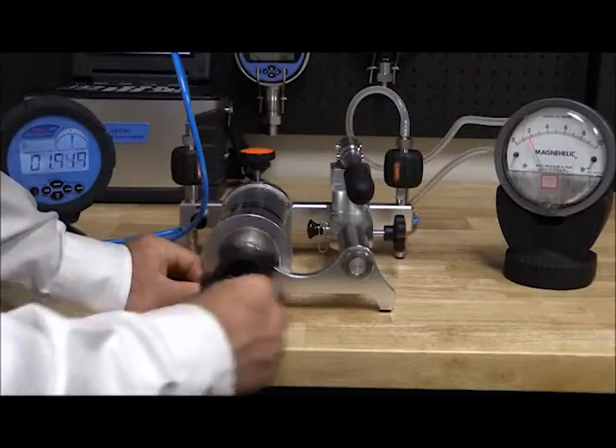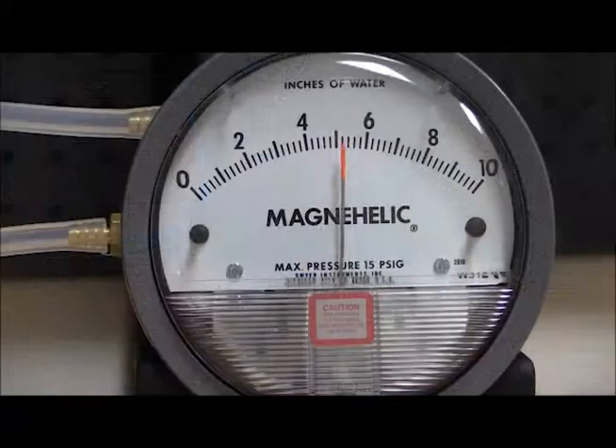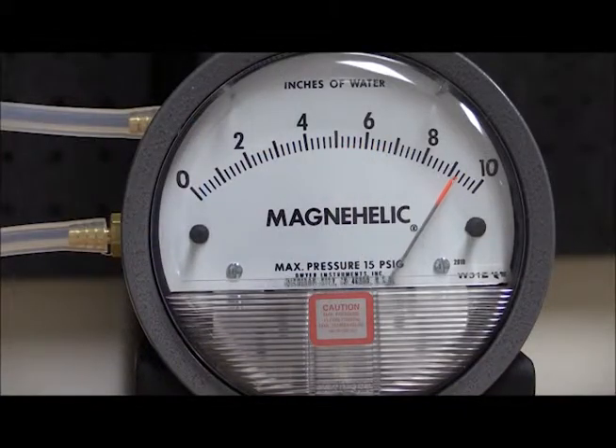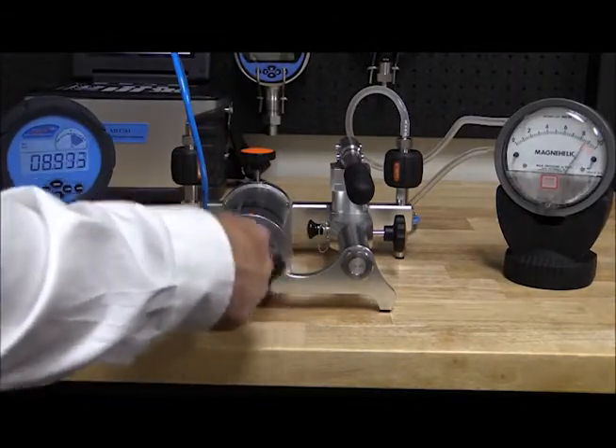Now we are ready to generate the pressure and record our results. Typically, three to five points are taken, both ascending and descending. By taking more than two points, we are able to check the gauge's linearity and hysteresis.